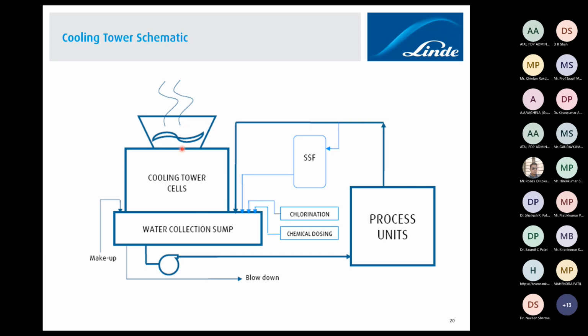You can always see a fan at the top to liberate the heat, and on the side louvers you will find air coming inside the cell, and at the bottom, the water you are throwing at the top deck gets cooled and converts into low temperature or cold water. So you have a sump, and then you can pump it back into the process. Basically the process unit is a set of exchangers, and after taking the heat the water becomes warm, so warm water comes back, and again we are fetching it, not on the sump, but basically on the top deck, and from the top deck it comes to the sump.